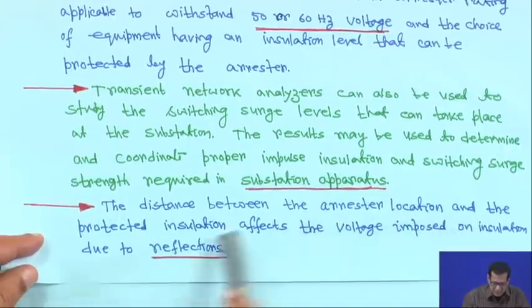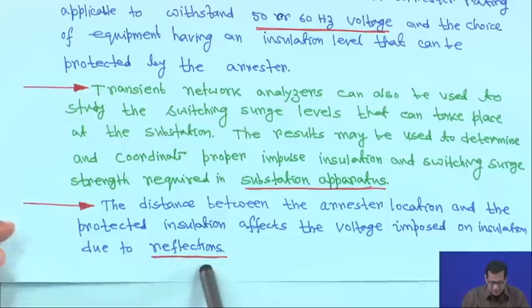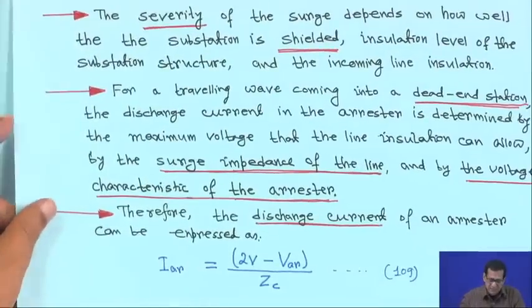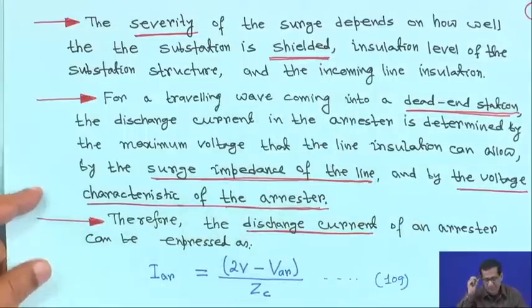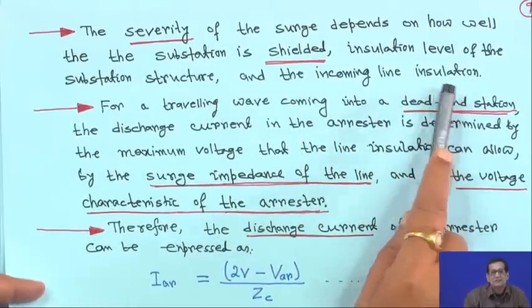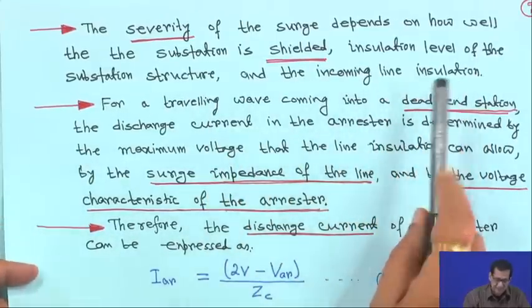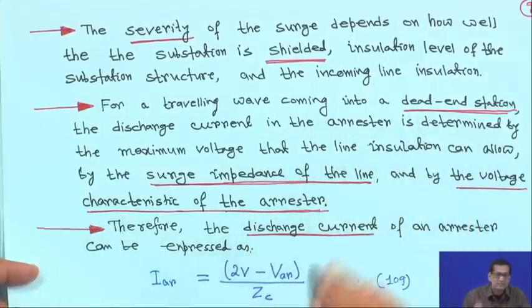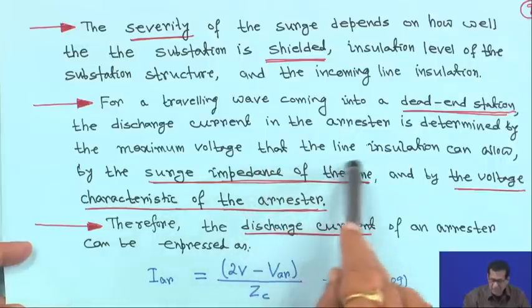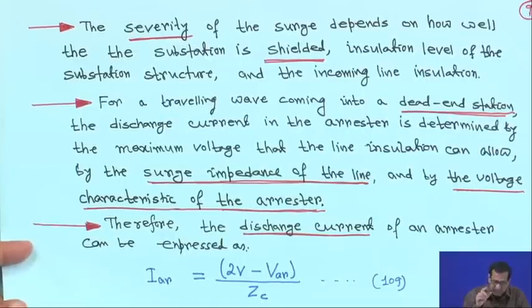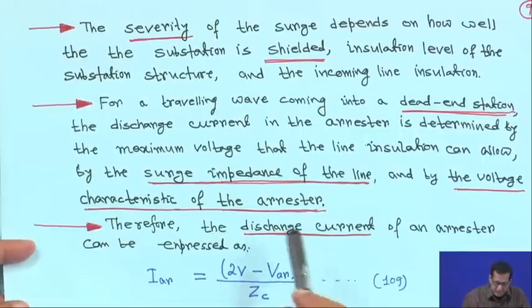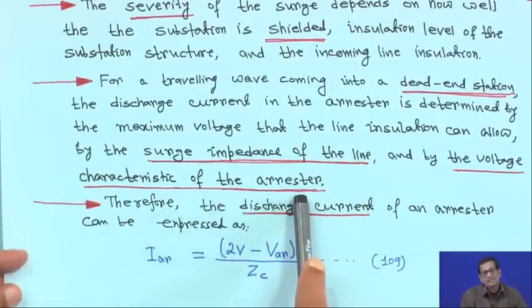The distance between the arrestor location and the protected insulation affects the voltage imposed on insulation due to reflections. The severity of the surge depends on how well the substation is shielded — that is, the insulation level of the substation structure and incoming line insulation. For a traveling wave coming into a dead-end station, the discharge current in the arrestor is determined by the maximum voltage the line insulation can allow.